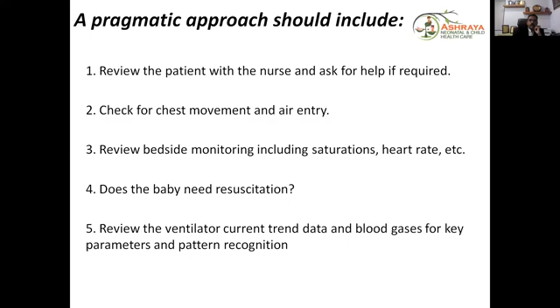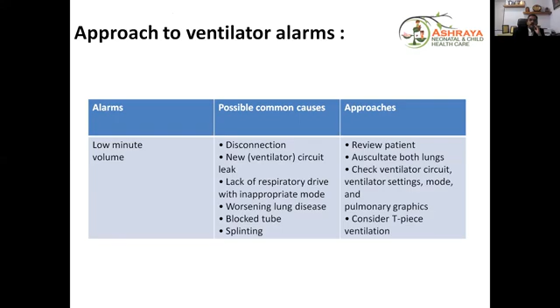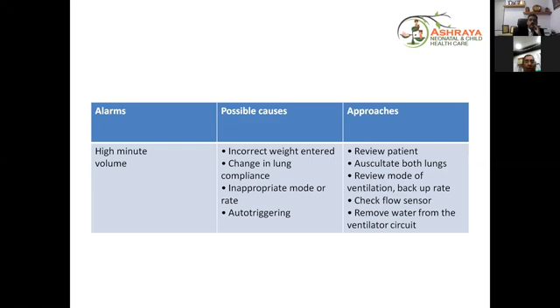So, approach to ventilator alarms: if there is a low minute volume, possible common causes can be a disconnection, a new ventilator circuit leak, lack of respiratory drive with inappropriate mode, worsening lung disease, a blocked tube and splinting. The approach should be to review the patient, auscultate both lungs, check ventilator circuits, ventilator settings, modes and pulmonary graphics, and consider a T-piece ventilation. High minute volume tells us there is an incorrect weight entered, a change in lung compliance, inappropriate mode or rate, or auto triggering. So again, review the patient, auscultate both lungs, review the mode of ventilation and backup rate, check the flow sensor, and remove water from the ventilator circuits.